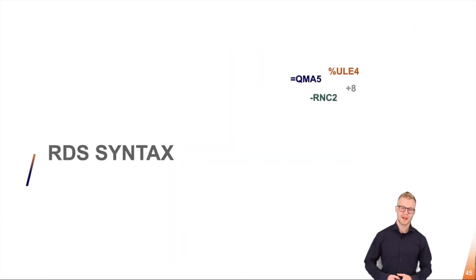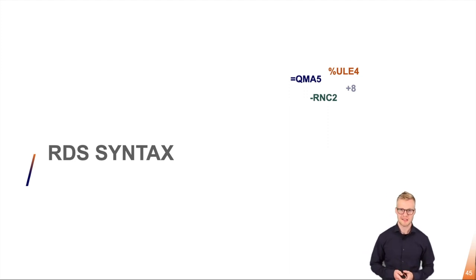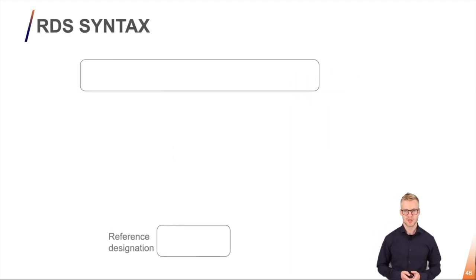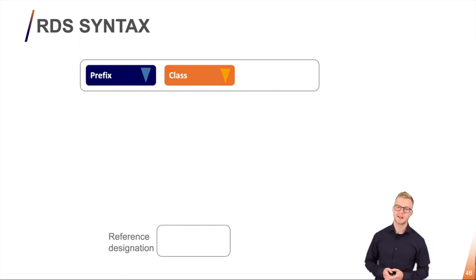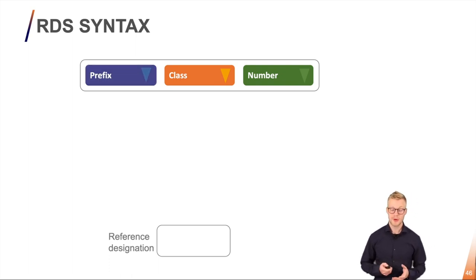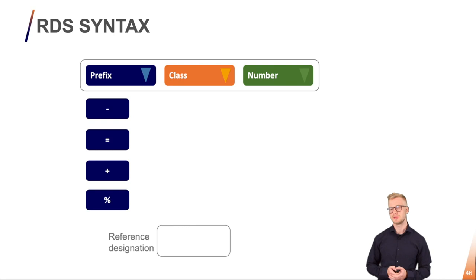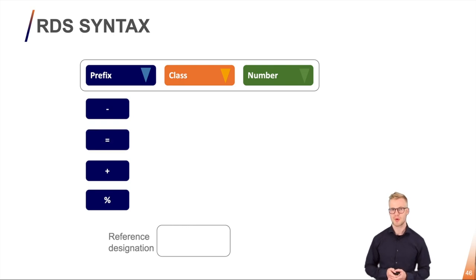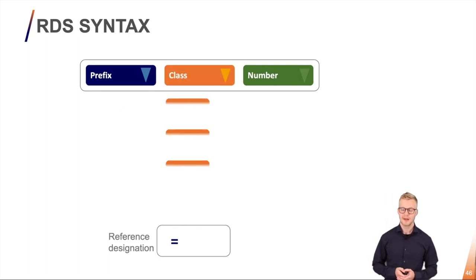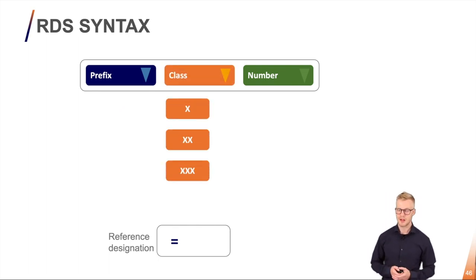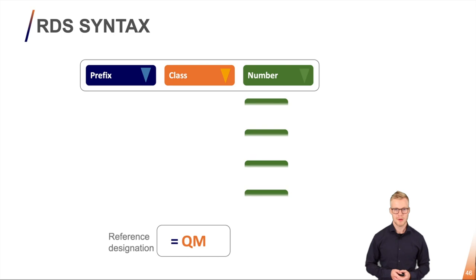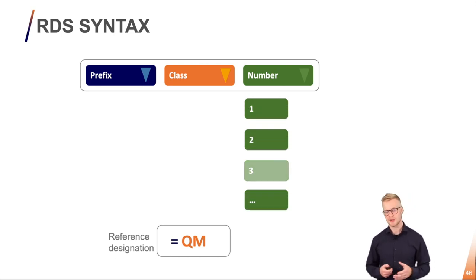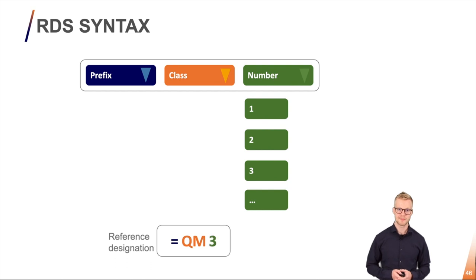So now we have all the elements that we need in order to create our reference designation syntax. Let's go through them. So first we have our prefix, then we have our classification code and lastly we have our number. So we already know about the prefix. These represent the aspects. I want to take a look here at the functional aspects so I'll pick an equal. Next thing I'll pick a classification code. I need a technical system so I'll pick a two-letter classification code. QM for example. And lastly I'll pick a number. Remember the number contains no meaning but since it's my third QM in my system I'll pick number 3. This is my single level reference designation.